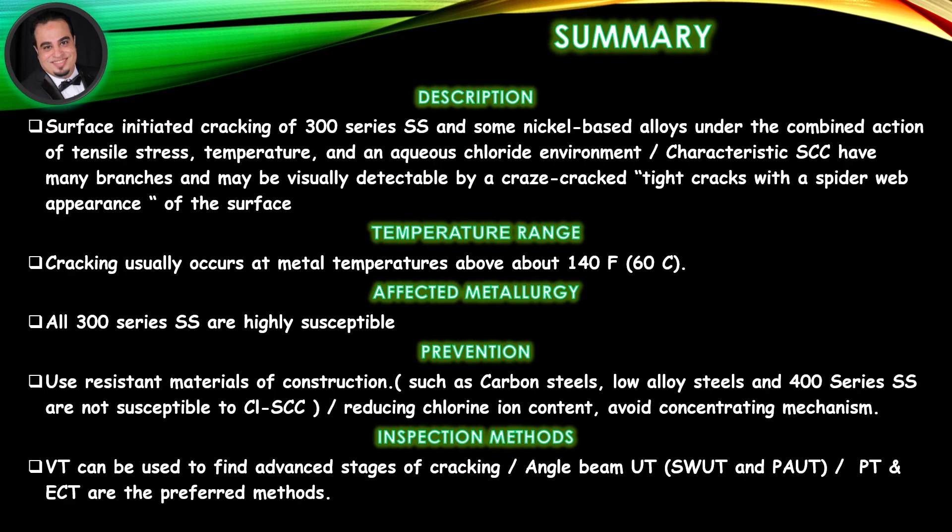Summary — Description: Surface initiated cracking of 300 series stainless steel and some nickel-based alloys under the combined action of tensile stress, temperature, and an aqueous chloride environment. Characteristic stress corrosion cracks have many branches and may be visually detectable as tight cracks with a spider web appearance on the surface. Cracking usually occurs at metal temperatures above about 140°F.